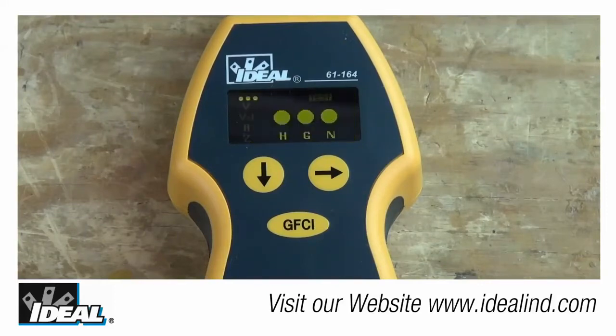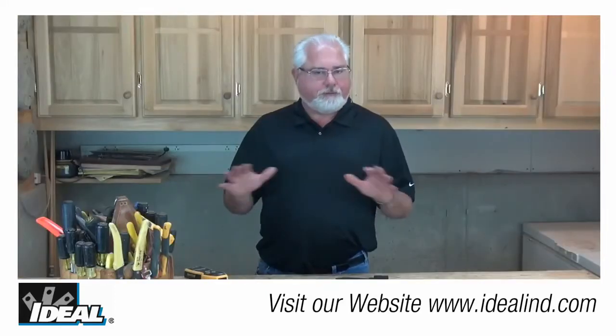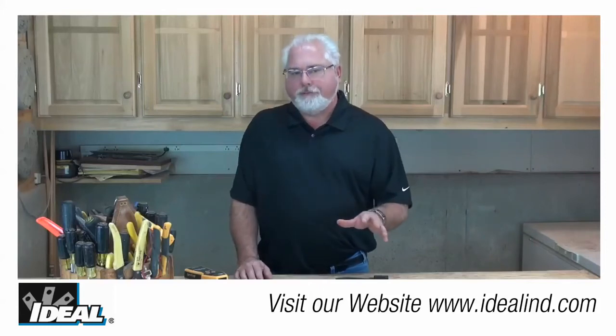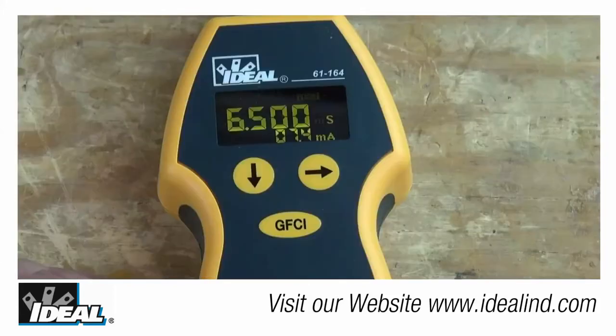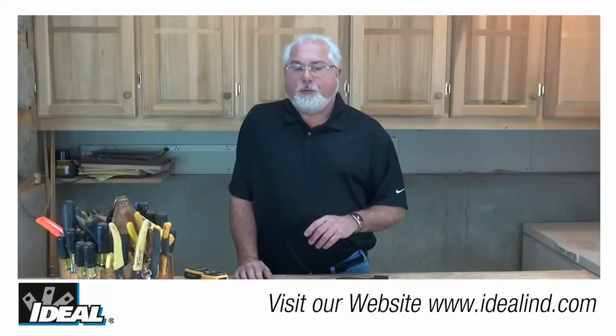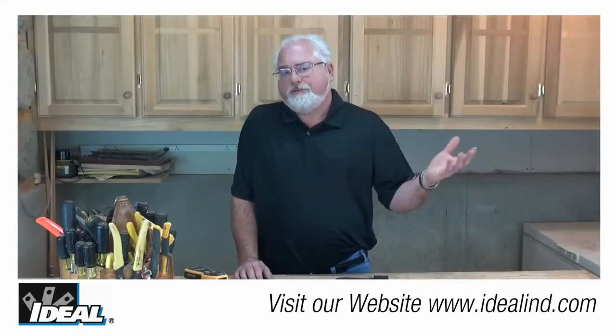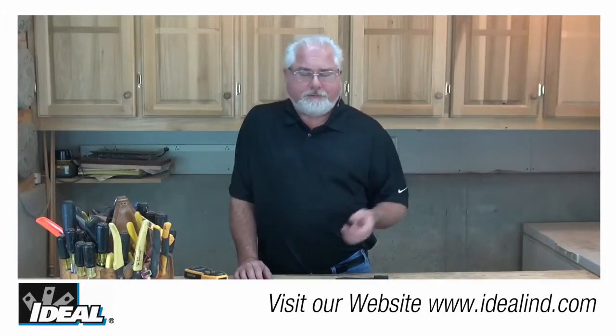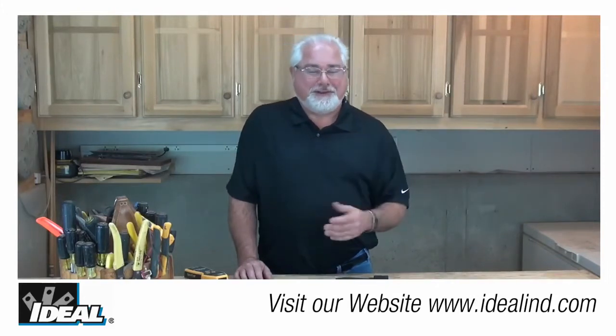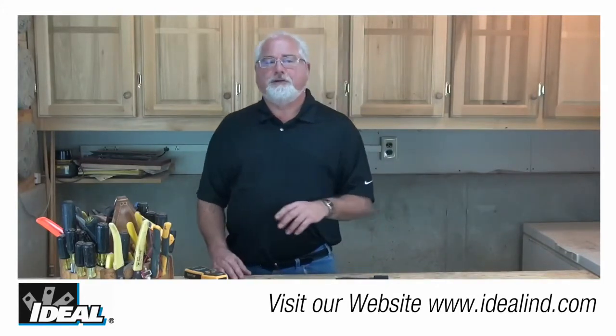Now, if the GFCI device fails to trip, the tester is going to terminate the test after 6.5 seconds, which is displayed as 6,500 milliseconds. And then further inspection should determine whether the GFCI device circuitry is faulty, the device is installed incorrectly, or maybe there is no GFCI device on that circuit.